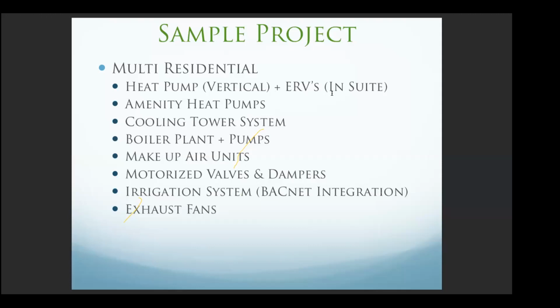Heat pumps and ERVs, typically in multi-res buildings over here at least, they don't end up putting controllers in every unit. So they typically leave those standalone. In some cases, we do end up doing that depending on what the developer wants. Typically, what happens in condo buildings is they let it be on its own. So in this scenario, if we assume that, then the heat pump is going to have its own standalone thermostat inside the residential suite. If it does not, then it has a controller and the thermostat is wired to the controller. And there's ERVs that are typically for the bathroom exhausts. They are just on a 30, 60, 90 or 10, 20, 30 timer switch.